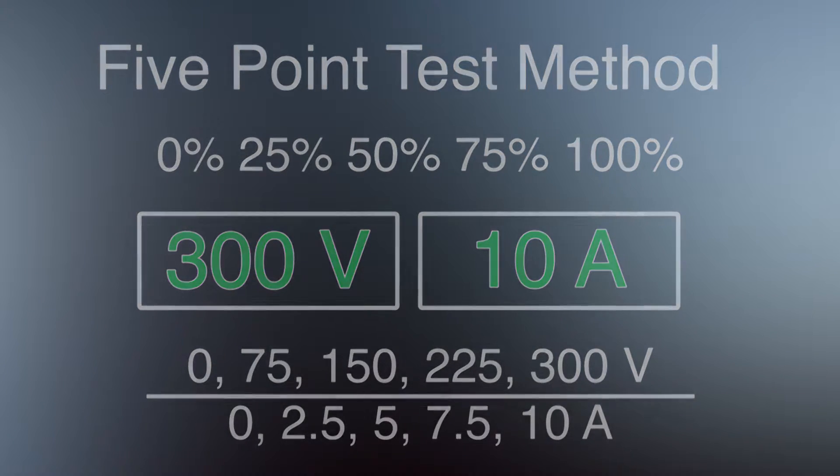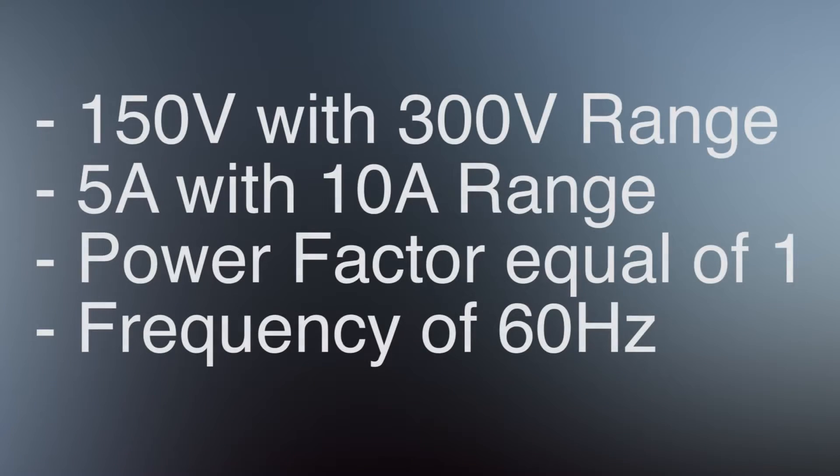For this analysis we will use a voltage of 150 volts to 300 volt range and a current of 5 amps with a 10 amp range, a power factor equal to 1, and a frequency of 60 Hertz. These values were chosen to be 50% values of the five point method and are just chosen to demonstrate one point of the five point method for accuracy testing. Only one point is chosen for the sake of time during this video.